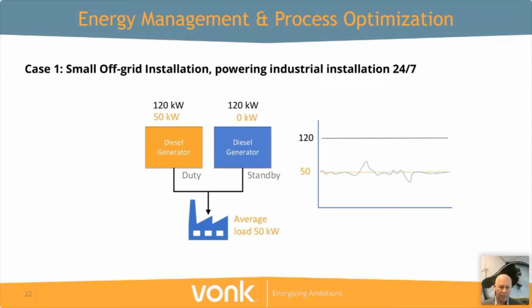The plant needs 50 kilowatts average of load. We have a diesel generator in place and a backup diesel generator. However, in this situation, it's not ideal because the diesel generator should run at least at 70% of its maximum load of 120 kilowatts, or 100 kilowatts in this case, and it only runs at 50 kilowatts. So that's not ideal.